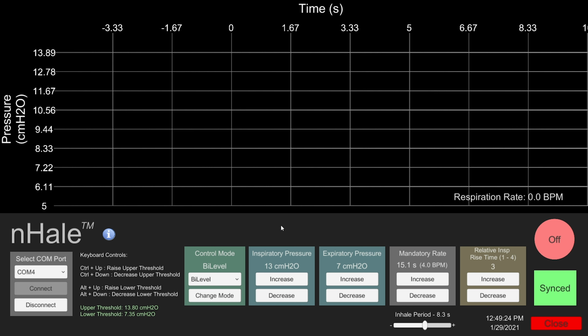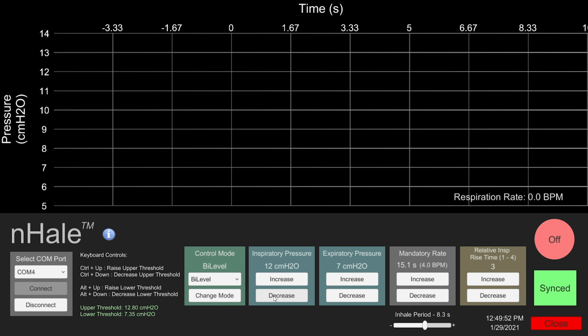On the y-axis, we have the display of the therapy pressure, and on the x-axis, we have a rolling window of time. Let's select the appropriate mode for therapy. If you would like to operate the nHale as a bi-level positive air pressure device, select BiPAP and click Change Mode. During bi-level pressure therapy, we can increase and decrease both the inspiratory and expiratory pressures using the buttons here. We can modify the pressures in 1 cm H2O steps from 4 cm H2O to 20 cm H2O. Let's increase the inspiratory pressure to a value that feels comfortable to our patient.